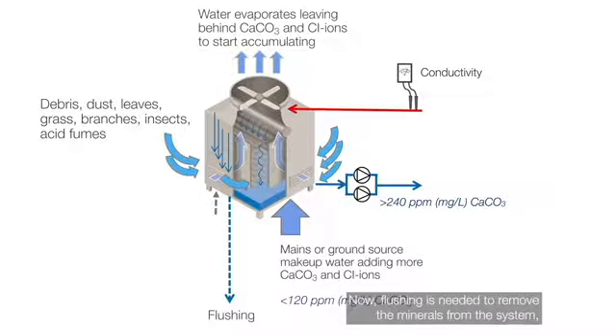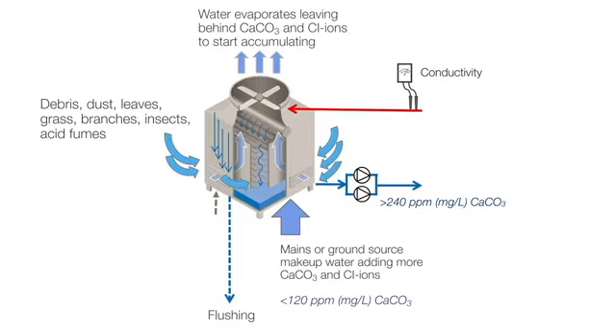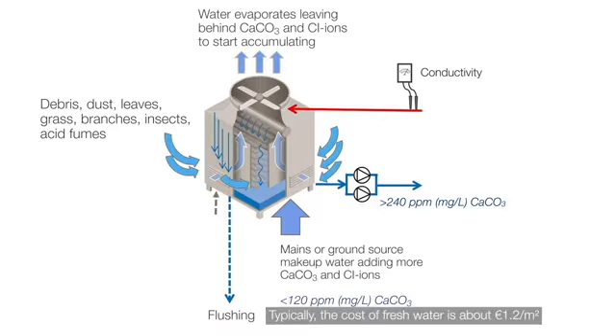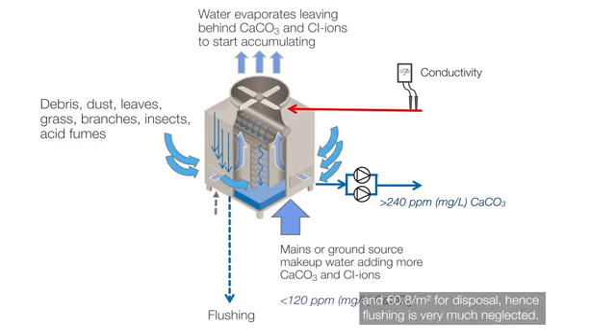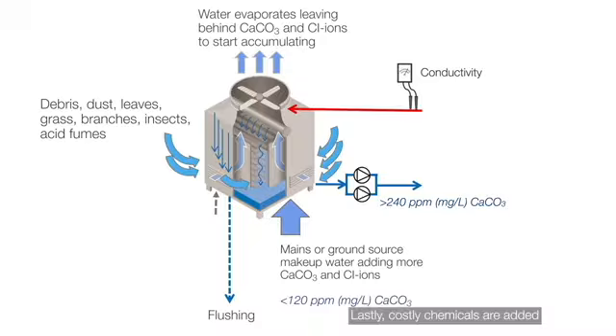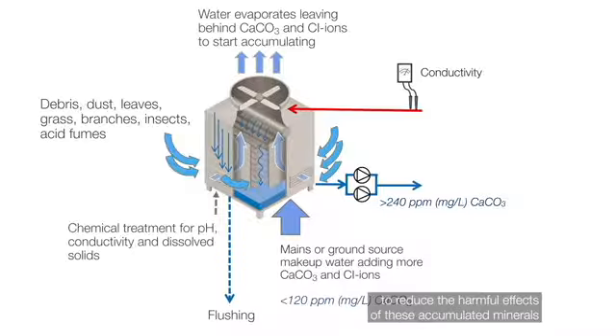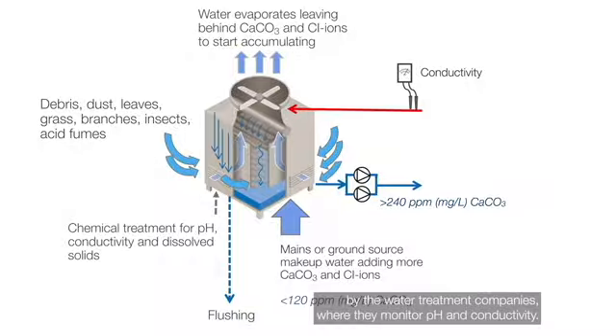Now, flushing is needed to remove the minerals from the system, but it is usually neglected due to high water costs. Typically, the cost of fresh water is about 1.2 euro per meter cube and 0.8 euro per meter cube for disposal. Hence, flushing is very much neglected. Lastly, costly chemicals are added to reduce the harmful effects of these accumulated minerals by the water treatment companies, where they monitor pH and conductivity.